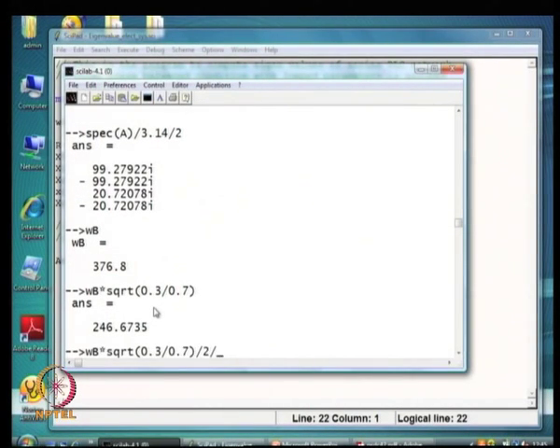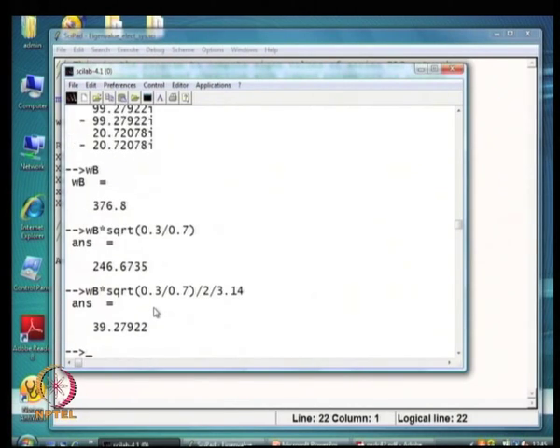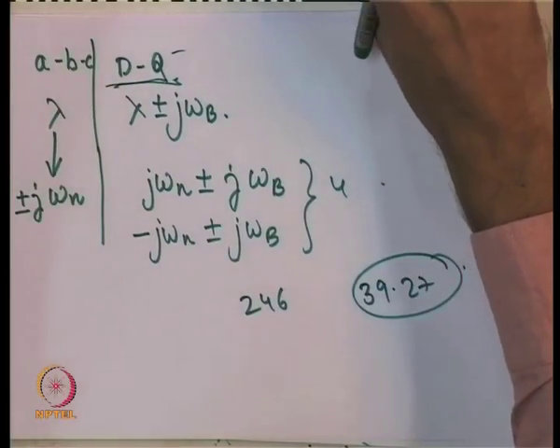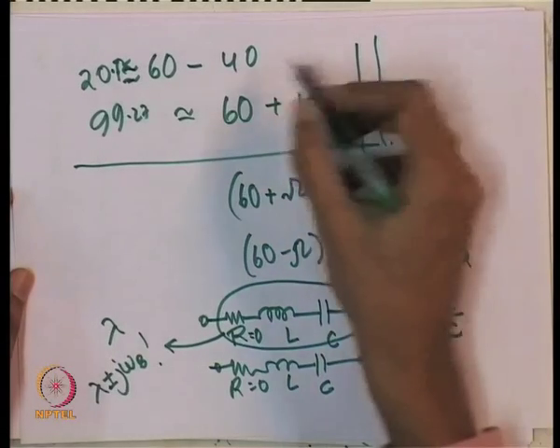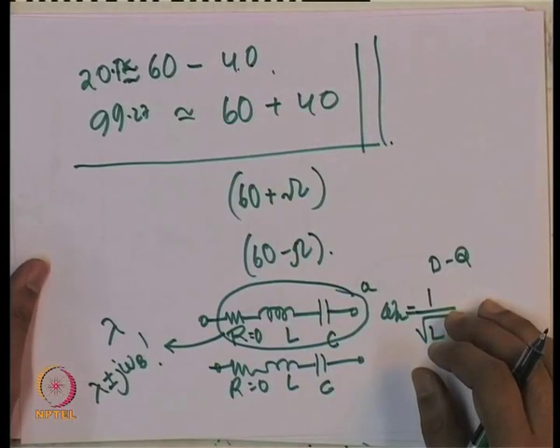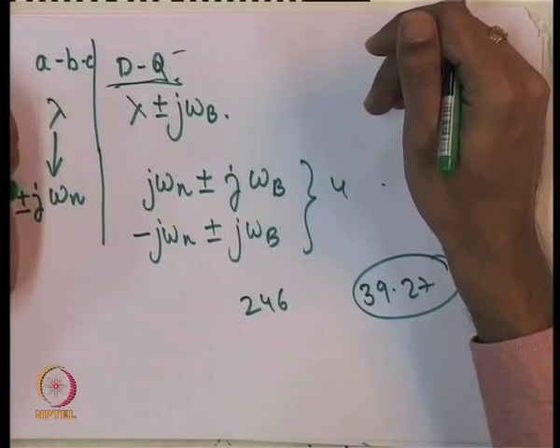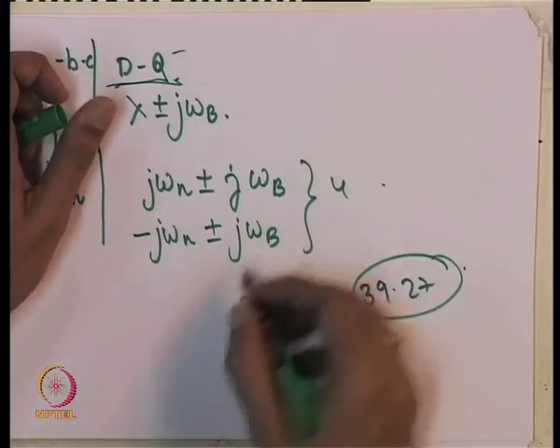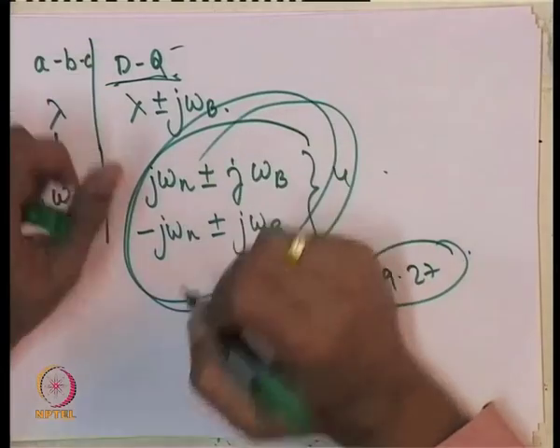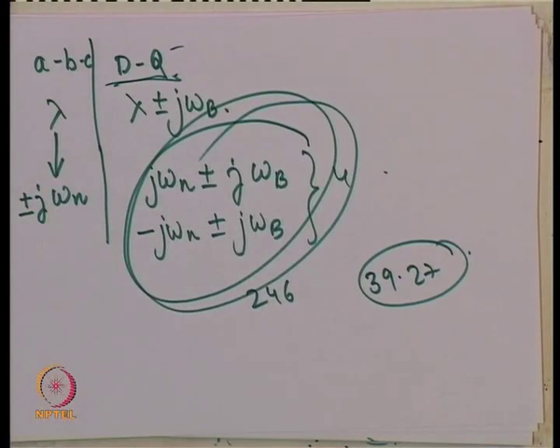Taking 246 radian per second and dividing by 2*pi gives a frequency of about 39.27 hertz. So the four eigenvalues obtained by the D-Q reference frame analysis correspond to 60 ± 39.27 hertz — approximately 20.73 and 99.27 hertz. This explains the eigenvalues seen on screen. If you have a series-compensated network, you do get oscillatory eigenvalues and interestingly some of them are sub-synchronous.